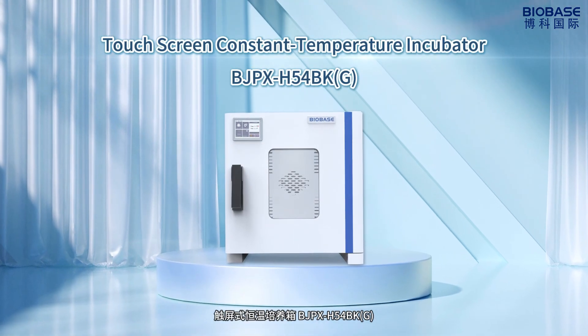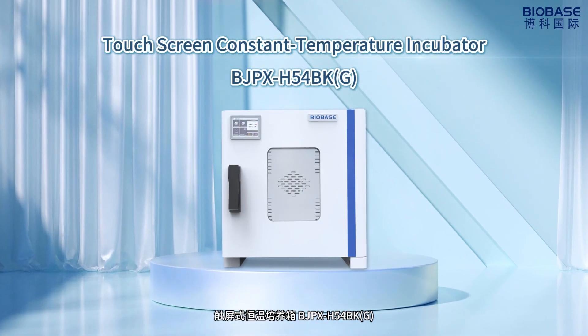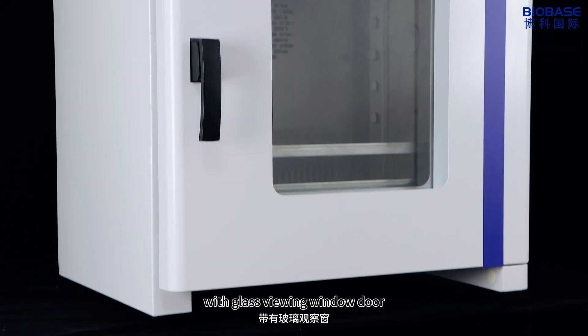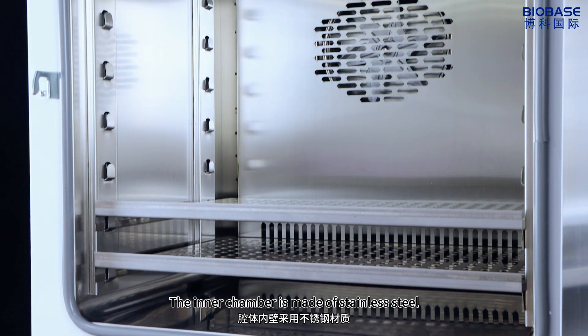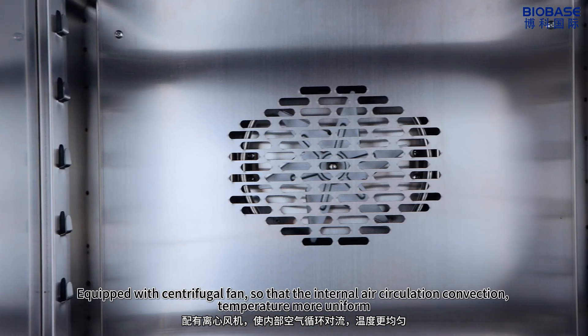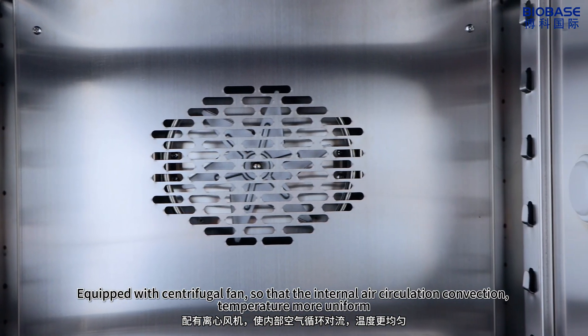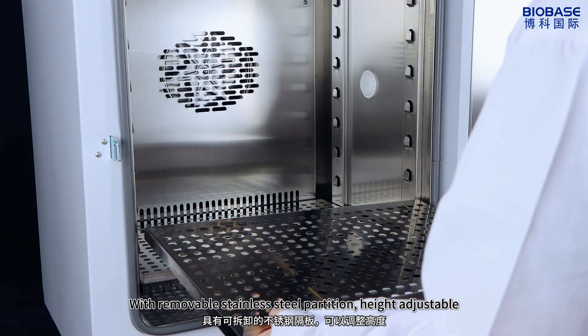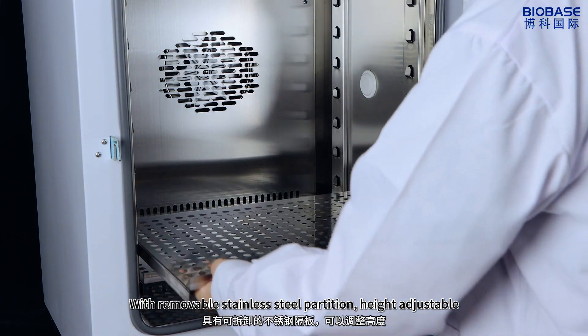Touchscreen Constant-Temperature Incubator BJPX-H54BK(G) with glass viewing window door. The inner chamber is made of stainless steel, equipped with a centrifugal fan so that internal air circulation and convection temperature is more uniform, with removable stainless steel partitions that are height adjustable.